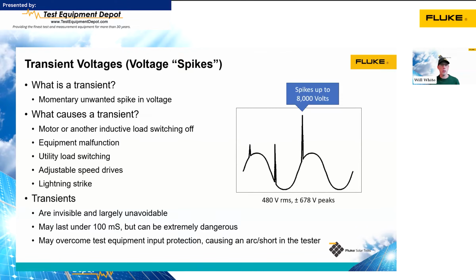And the important thing to take away from this slide is this last bullet, that if you have test equipment and you're doing voltage testing and you get a transient voltage spike, that could overwhelm the meter. It could damage the meter. It could cause a safety hazard to the technician. So you need to make sure that you have test equipment that is able to withstand these transient voltage spikes.